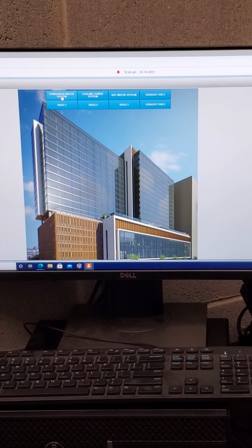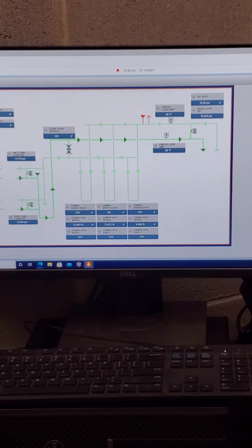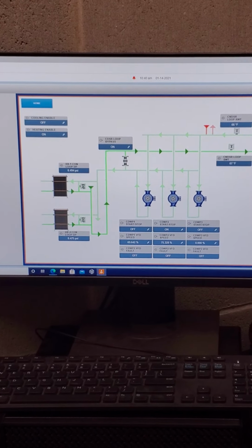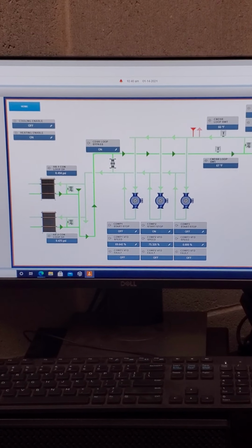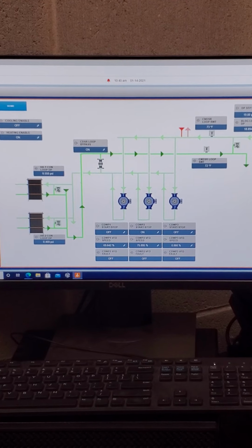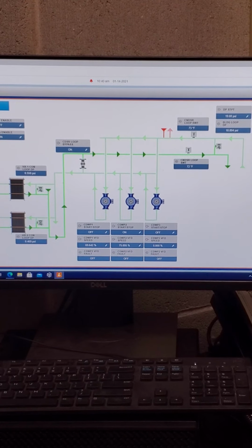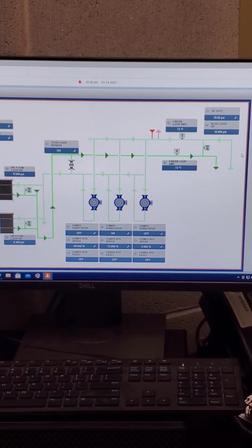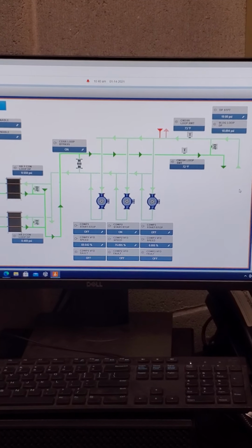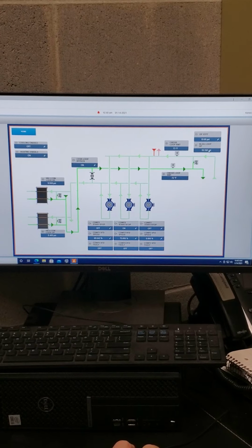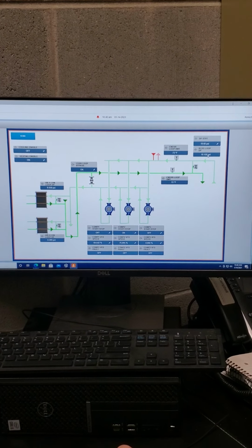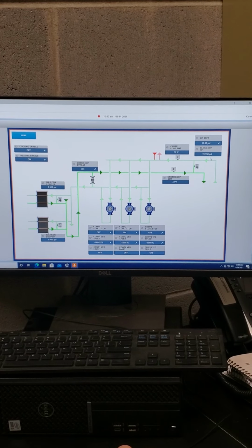Clicking on a link here, we'll start with the condenser water. It'll bring you to a page. It'll take a second to load everything. It'll usually show you values as soon as it opens that are from like a cached previous level. So sometimes it'll show you something and it'll change real quick. That's just the normal functionality. These are moving in real time. You can see the building DP loop is changing every so many seconds.